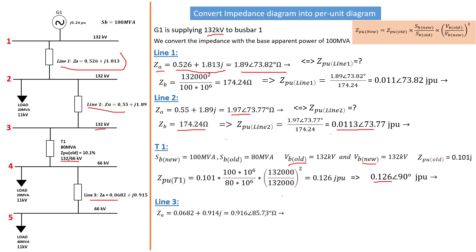As always we convert our actual impedance into polar form. The interesting thing now is our zone voltage V base for the zone is now 66 KV, no longer 132 like in the previous bus bar. From there we know the formula for ZB: ZB formula is VB square over SB new which is the base MVA that we are calculating for the entire network. We found a ZB of 43.56 ohm.